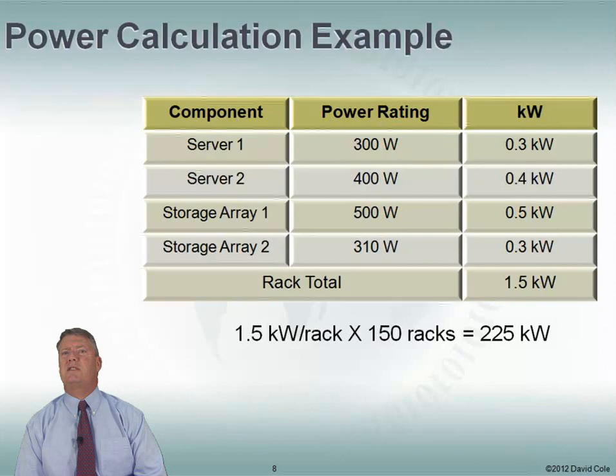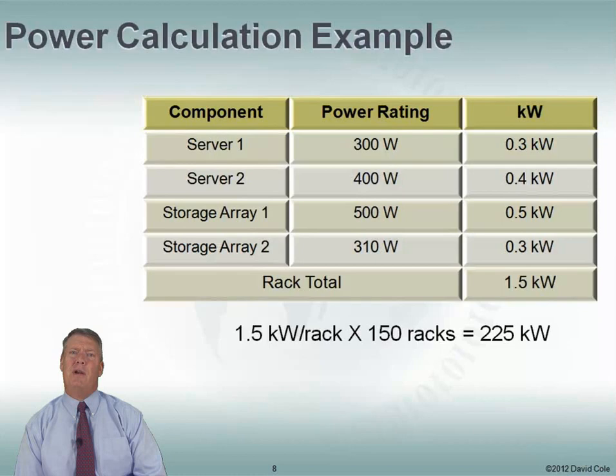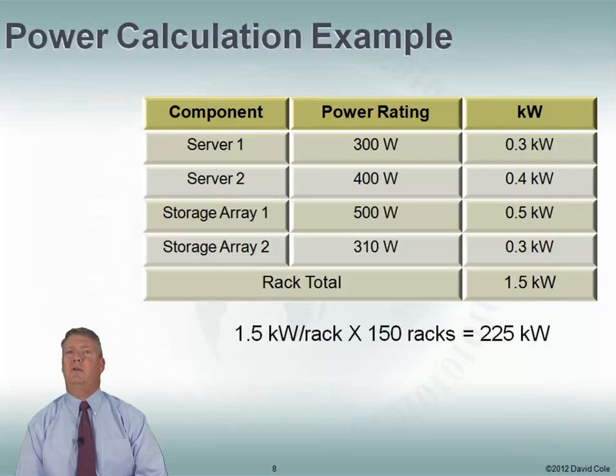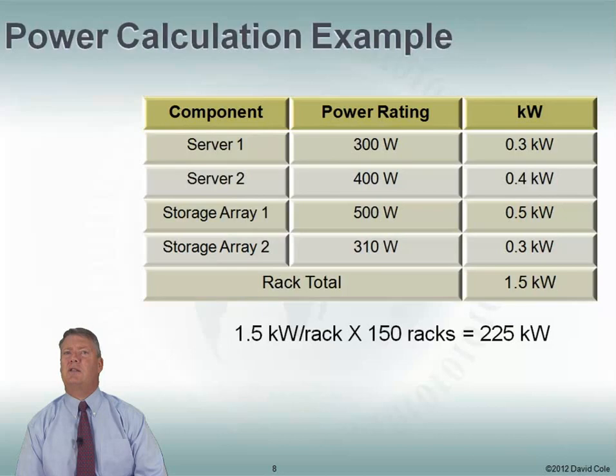Let's put this together in a grid, and ideally we want to do this on a rack-by-rack basis. If we've got a standard rack and spend a little time figuring out how much power it's going to draw, and most of our racks are going to be the same, it makes our calculations much easier. For example, let's say we have a couple of servers and a couple of storage arrays — total at this rack is one and a half kilowatts. With 150 racks, that gives us 225 kilowatts. But this is only our critical load.